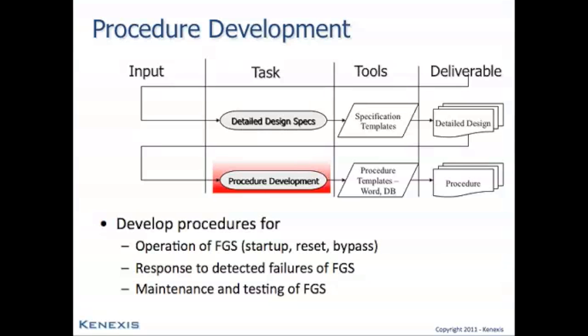Procedures that need to be developed include operation of the FGS, what needs to be done to start the system up, what needs to be done to reset the system after it has been activated, and under what circumstances the system will need to be bypassed and how those bypasses will be performed. During the development of these procedures, sometimes shortcomings in the design are evidenced, and the procedure development requires revisiting earlier phases in the safety life cycle to include new equipment to allow things like bypasses and resets to be performed while the system is online and functioning.